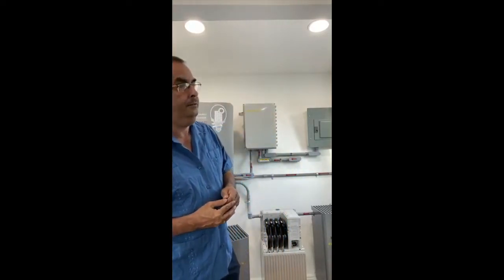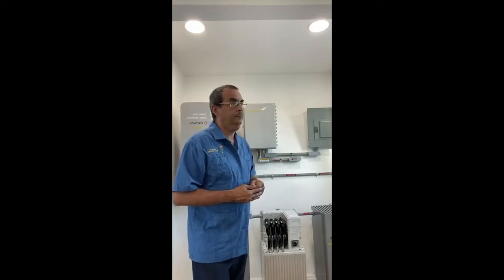Anna's asking if she can connect multiple different outlets in different rooms and designate what will be used during a power outage. Absolutely, we can designate a critical load panel, and it doesn't have to be all in one area, it can be many different areas of the house. You take circuits from different areas: from the kitchen you get your refrigerator, from the hallway and rooms you get the lights, you get the plugs from the living room you want to keep on, you want those ceiling fans across the house to stay on, the air conditioner in the den you want to keep on but not the main house. You choose, you pick and choose. We put them into one critical load panel, up to 200 amps, which is a whole home generator, so we can run a lot of power off that critical load panel.